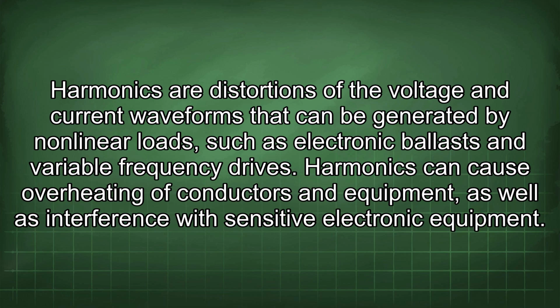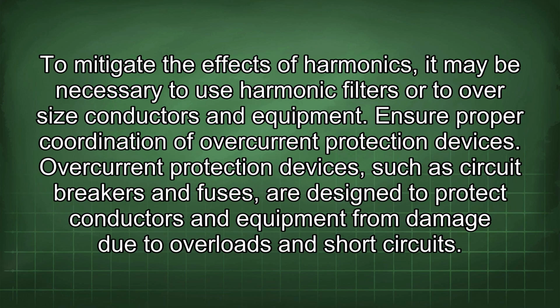Harmonics are distortions of the voltage and current waveforms that can be generated by nonlinear loads such as electronic ballasts and variable frequency drives. Harmonics can cause overheating of conductors and equipment, as well as interference with sensitive electronic equipment. To mitigate the effects of harmonics, it may be necessary to use harmonic filters or to oversize conductors and equipment.